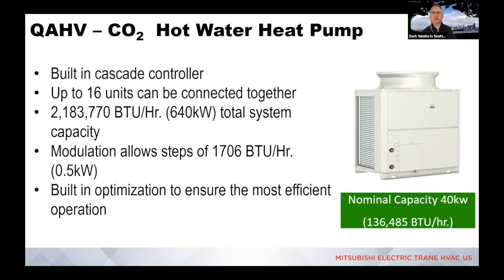So on the large heat pump hot water system, are any integrated smart controls available or considered to reduce peak demand and preheat to move the peak load earlier? I believe so. Just so I make sure I understand the question right, are we being asked if we basically have demand response capabilities with this unit to produce hot water during the best possible times? Or predictive, Joe says yes, demand response, and grid interactive hot water heaters.